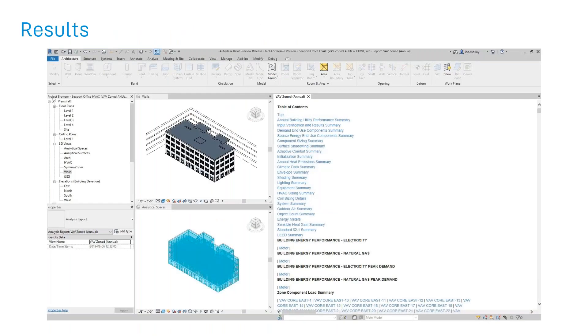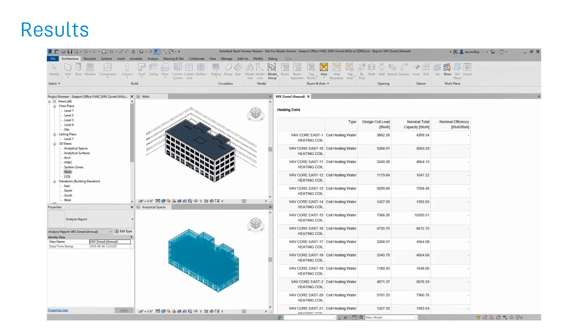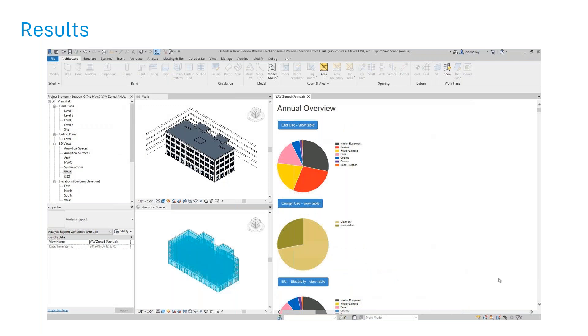In terms of GBXML, this is where we're using the hydronic loop information and zone HVAC equipment. We've added some new parameters — it's not strictly exactly GBXML currently, but we have been talking to Stephen and the board about proposing this as an extension. Although we're using EnergyPlus, we think it's pretty agnostic — these equipment relationships are the same regardless. On the results side, you get the classic sizing perspective outputs — the standard EnergyPlus report with information on boilers, chillers, fans, pumps — plus total building energy outputs.